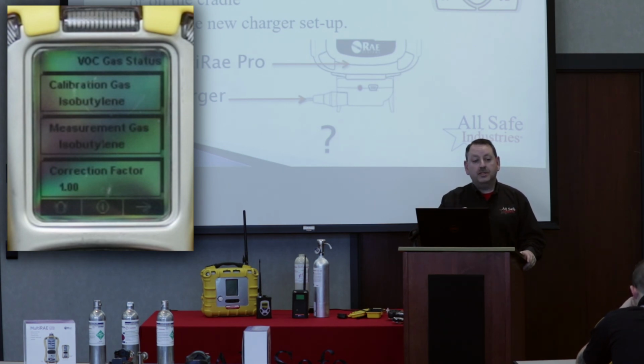If someone were to go into the menus, which I'm going to show you how to do, and reset the correction factor to get a more precise reading, this is the screen you'd come to see if that correction factor has been changed. And it will tell you what that factor is. Okay? So side note, if I've talked too long, after 30 seconds, your screen will want to go back to page 1. If it does that, just hit your arrow button until you're caught up to the page that we need to talk about next.